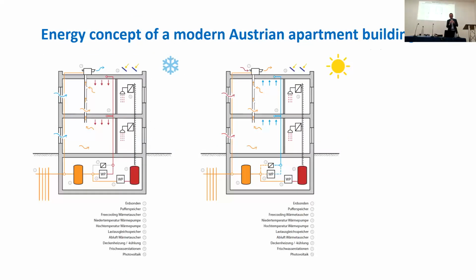This is the system for residential houses, which I think works very well. We are doing it now as a standard already. So a residential house with heating and cooling from the ceiling in the residential area, I'm much more a friend of this because of the condensation risk and because of the comfort risk from the floors. Again, a borehole heat exchanger field is feeding the heat pump for heating. The low temperature heat pump for heating is feeding the high temperature heat pump for domestic hot water. During the winter, we heat with this. During the summer, we cool with this, but only free cooling.